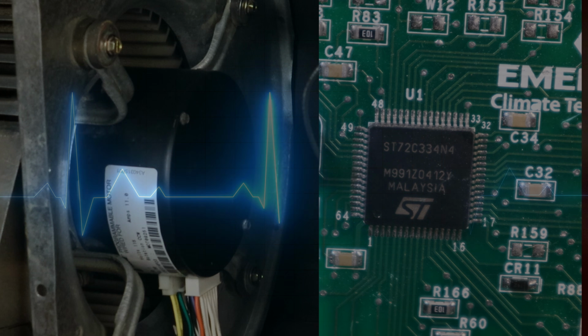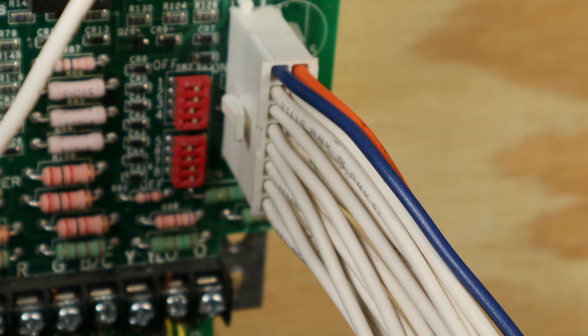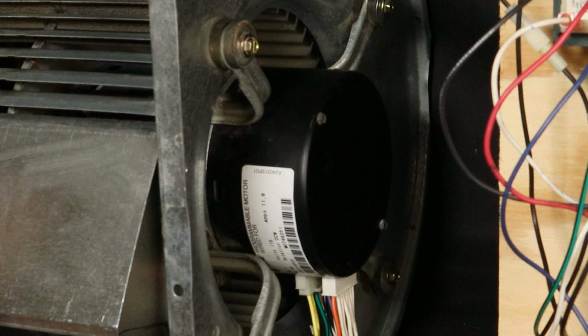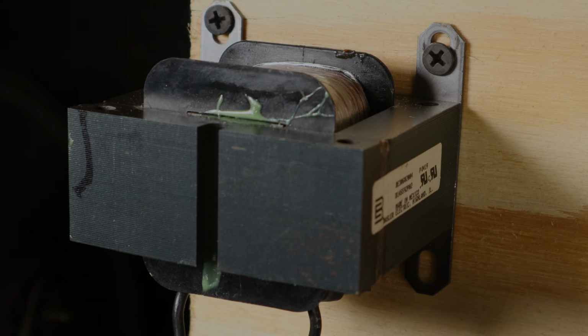They're not drifting away from one another and miscommunicating. Now, the low voltage isn't the only thing that needs to be cleaned up. These motors, when they're running, their electronics rapidly switch the power on and off thousands of times a second, and that switching creates electrical noise that can travel back into the wiring of the house itself. So you might see something that looks like this.